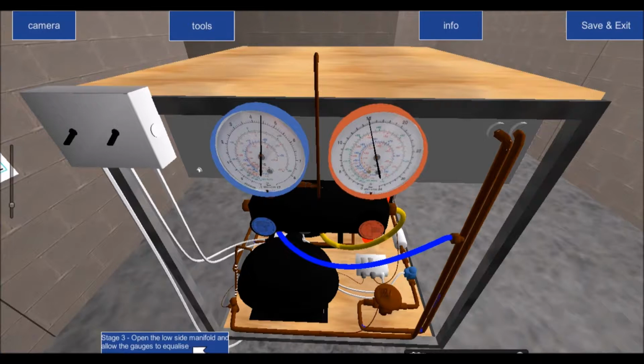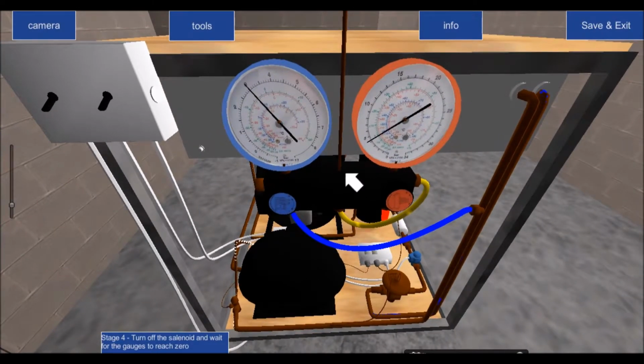Next it says open the low side manifold and allow the gauges to equalize. So watch. Effectively what you see here is the gauge went down from 15 bar to just 4.5 bar, and this one should be around the same, around 4.5 bar. The two pressures equalize. So this is saying 3 bar, but in real terms, if this says 3 bar, this will say 3 bar. If this says 4 bar, this says 4 bar. So the pressures will equalize in real terms across. The high pressure will come down to the low pressure.